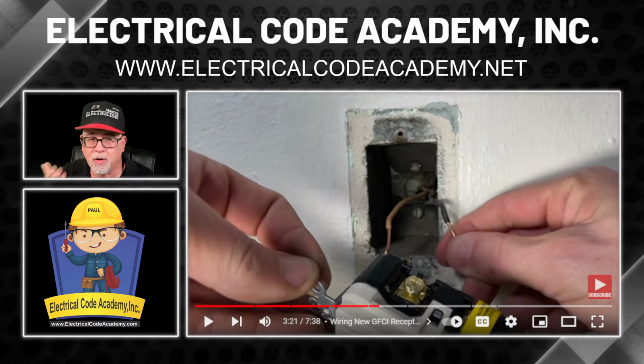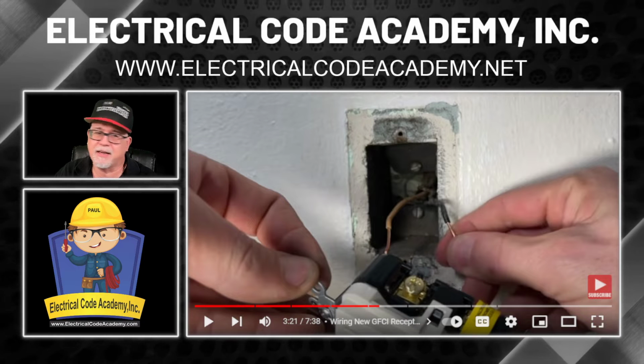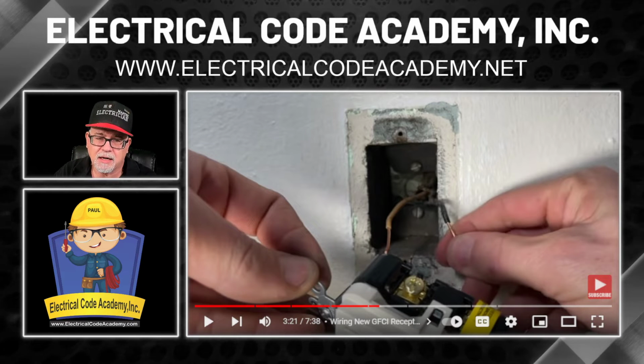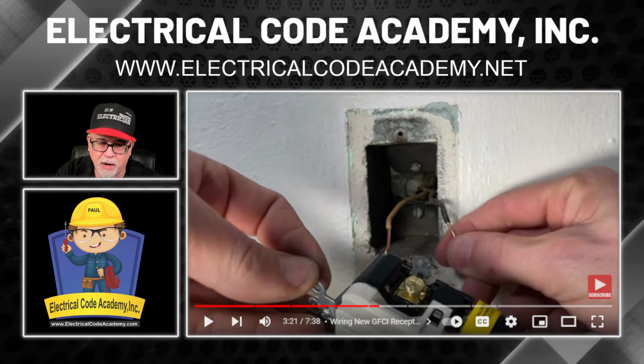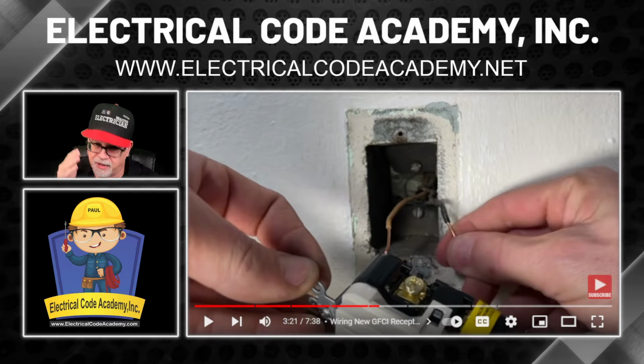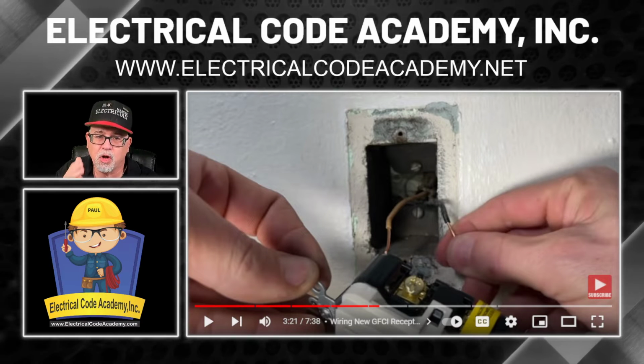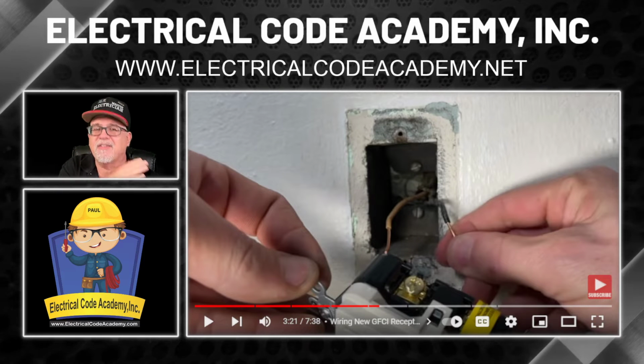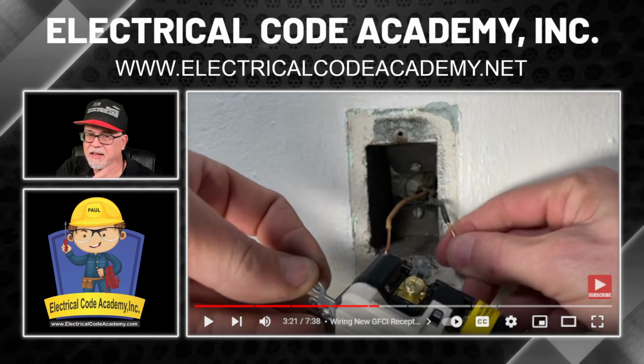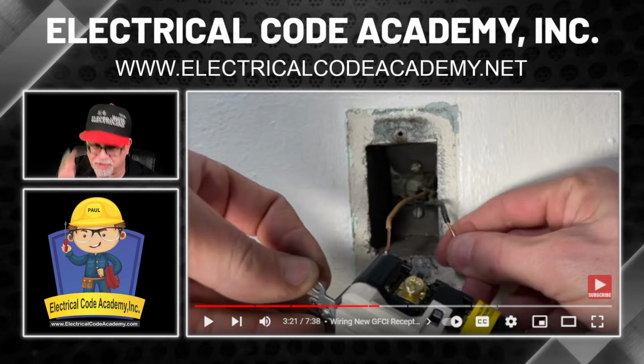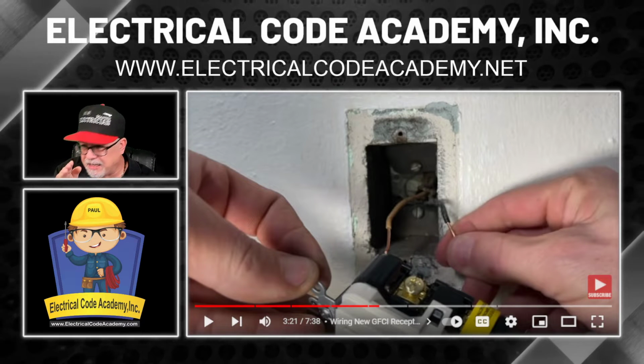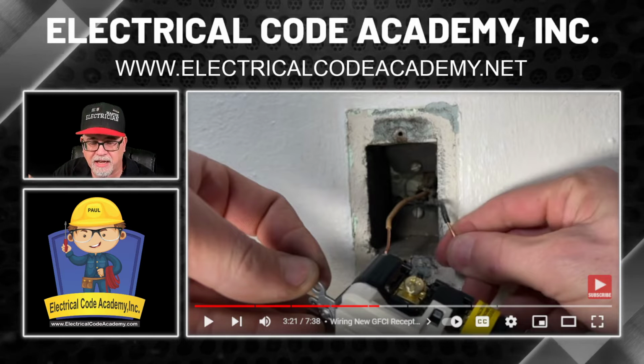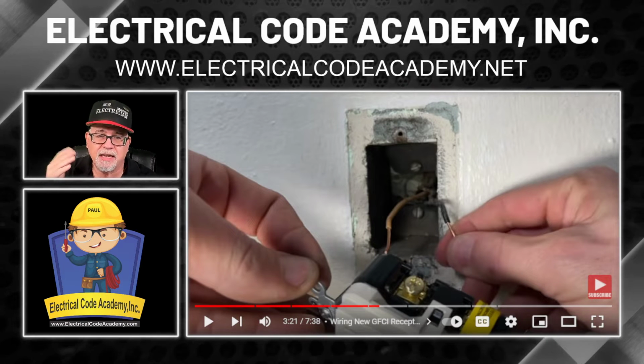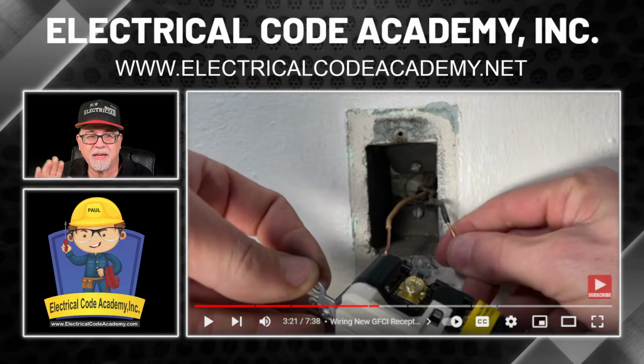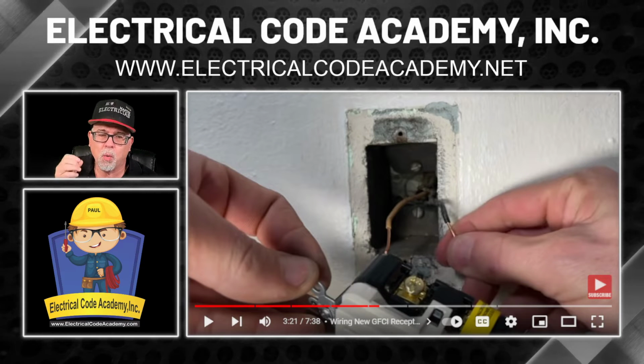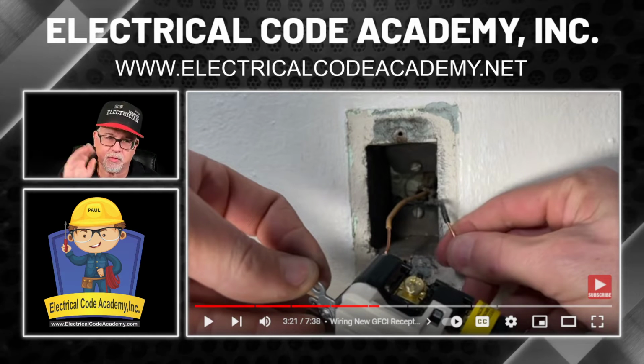Or maybe this is the only receptacle that he's wanting to do that. And who knows what the other ones are. But again, bear in mind that since there's only two wires here, this is either the individual branch circuit to this location, or it's at the end of an existing branch circuit. And this is not going to do anything for the receptacles upstream. It's only going to protect this receptacle. And since he's not running any downstream, he's not using the load side of this device, then this is either the end of the line or whatnot. So just keep those things in mind. But we will talk about what to do when I have multiple receptacles in a room a little later.